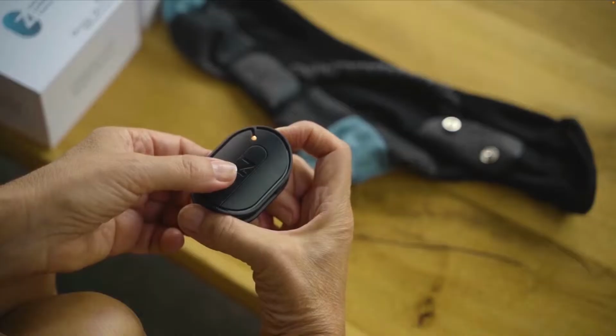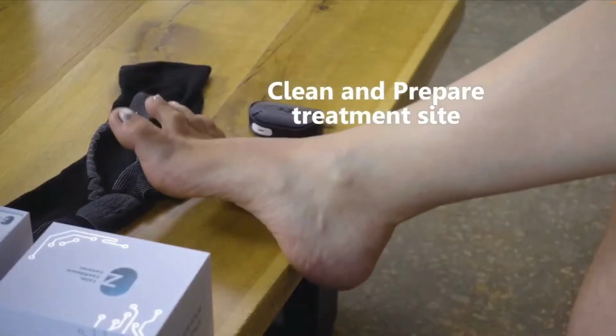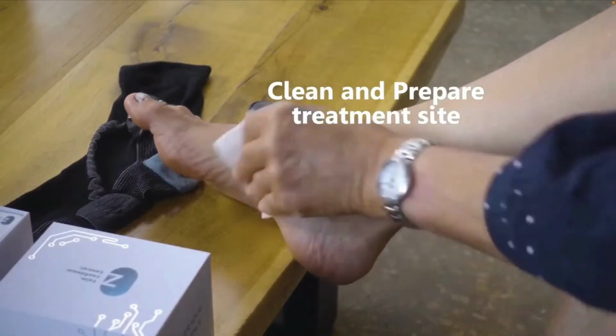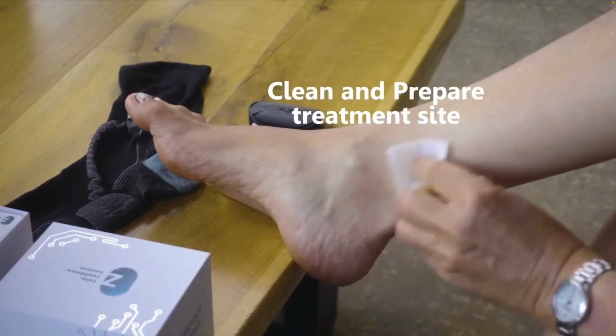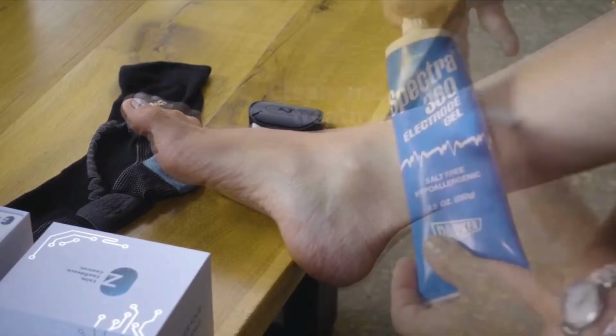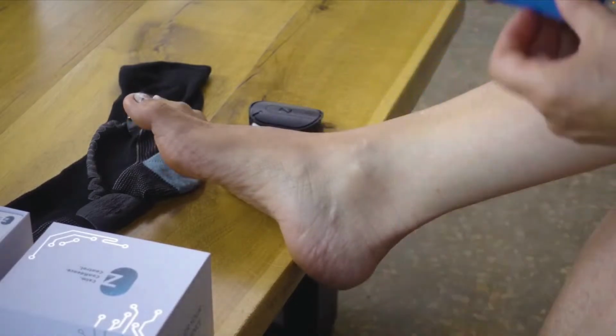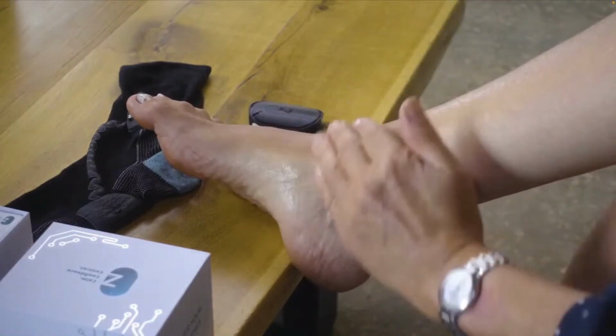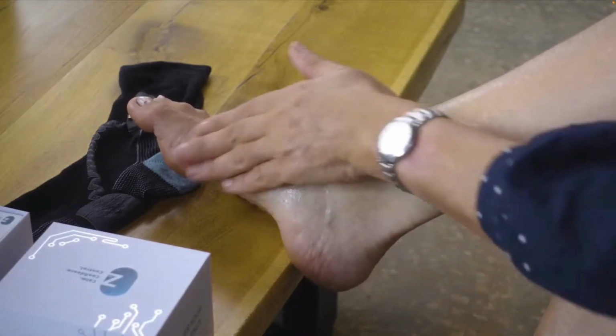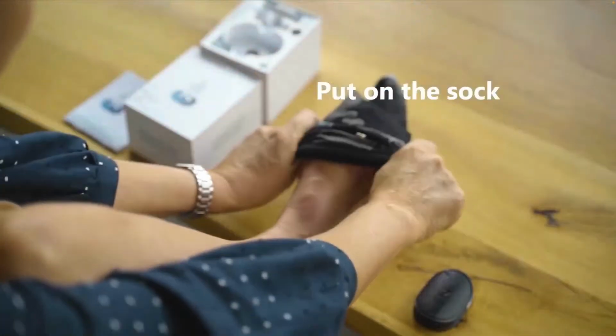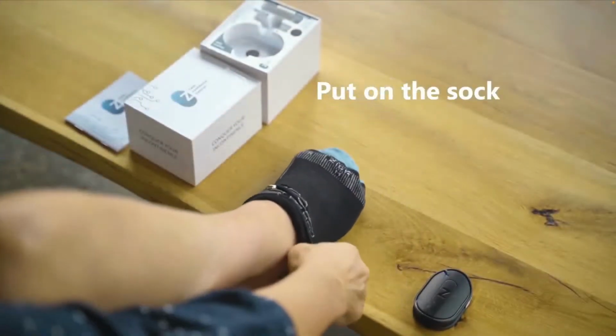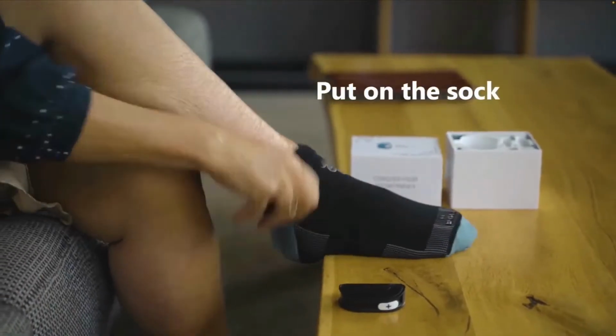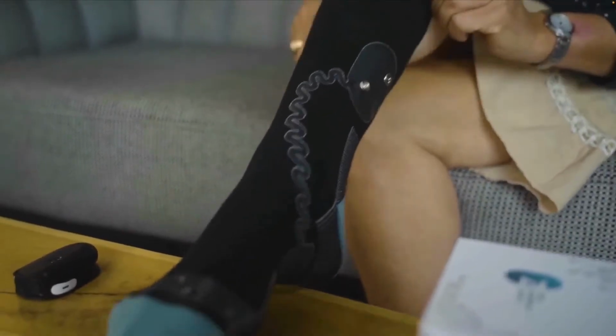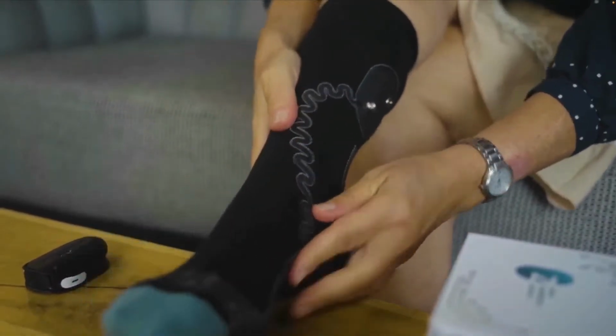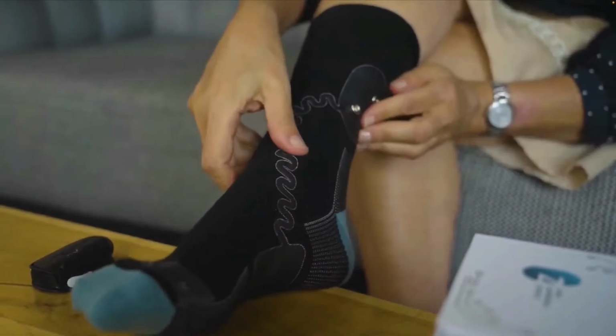We are ready to begin the treatment process. Clean and prepare the treatment site by washing it with soap and water. Gently dry the site. For increased performance, you may choose to apply conductive electrode gel. The gel should be applied directly to the skin at the treatment site. Now, put on the sock as you would any other sock. Make sure that the toe and ankle area are lined up properly and pull the sock completely up on your leg. Make sure that both embedded electrodes are in direct contact with your skin.